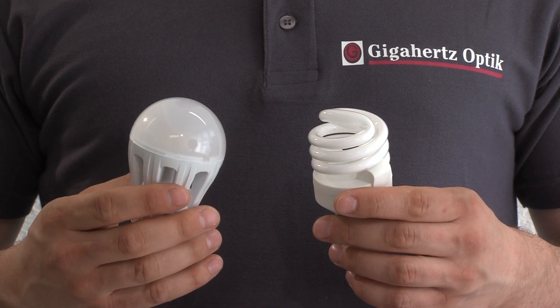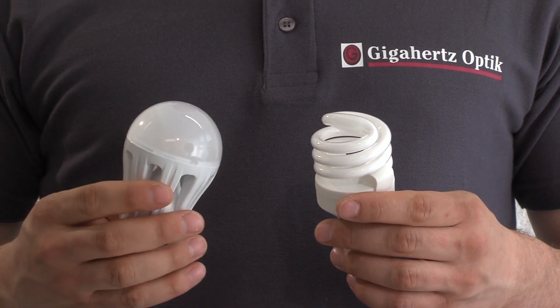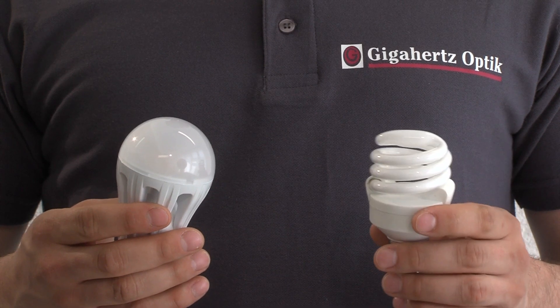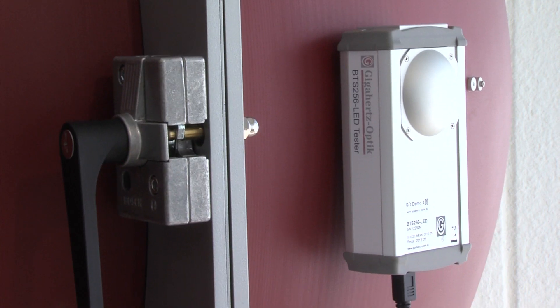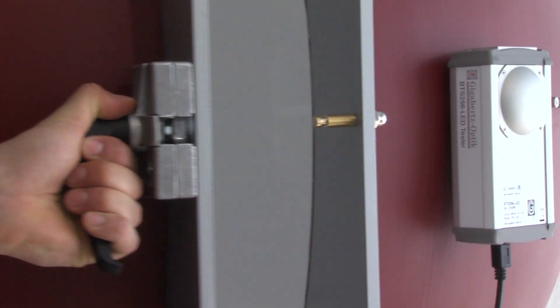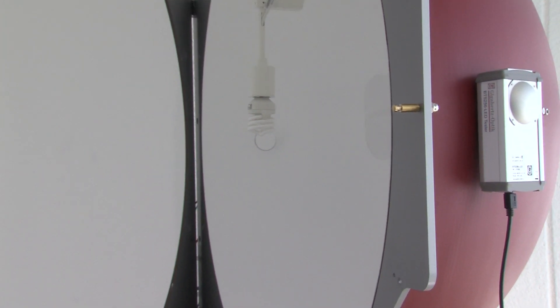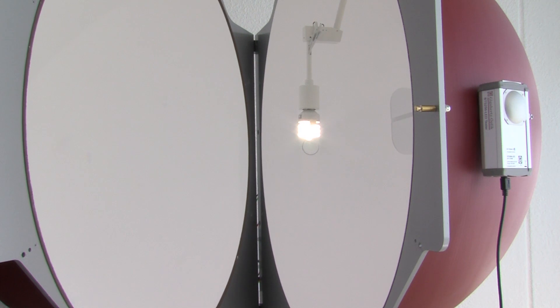When measuring luminous flux of LED lamps and compact fluorescent lamps, the source must be placed in the center of the integrating sphere. Integrating spheres designed for measuring lamps inside the sphere open and close and include a lamp holder mounted inside the sphere.